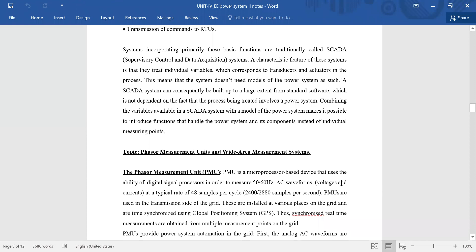Then we have phasor measurement units and wide area measurement systems. How are we using that now? The phasor measurement unit, that is a PMU, is a microprocessor-based device which has the ability, using digital signal processors, to measure 50 or 60 hertz AC waveforms, the voltages and currents, at a typical rate of 48 samples per cycle, or 2400 or 2880 samples per second.